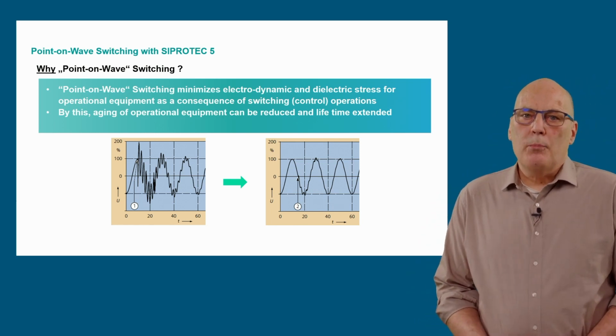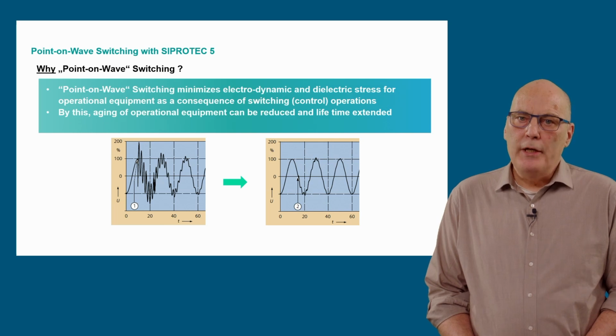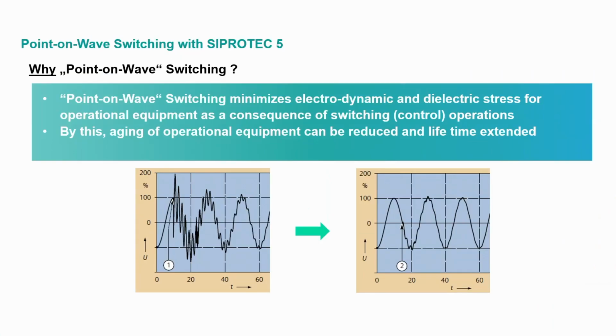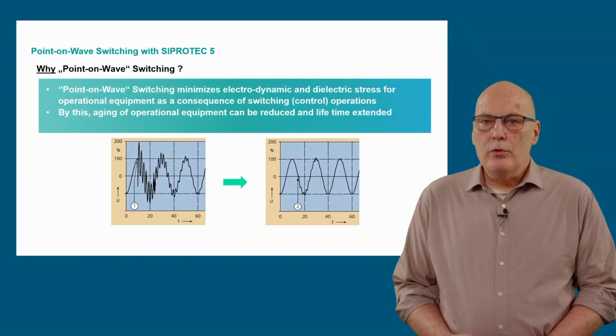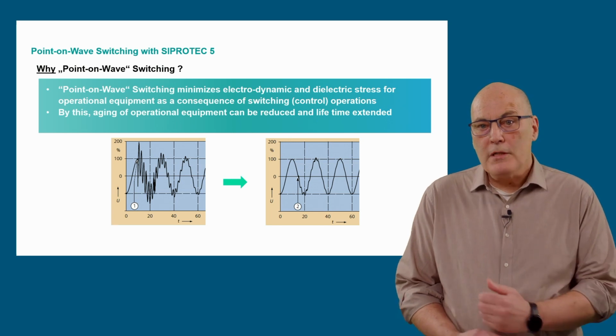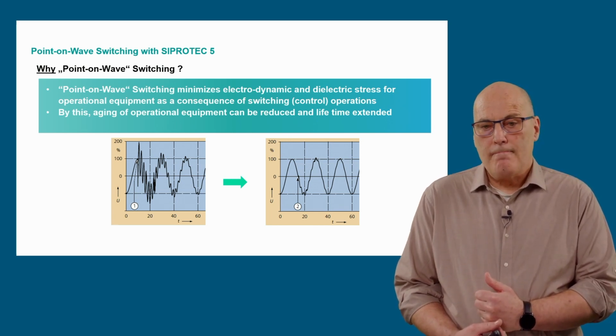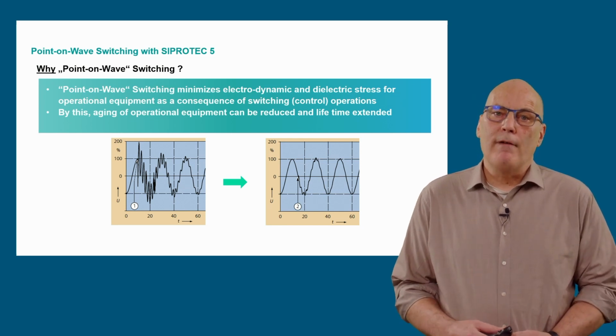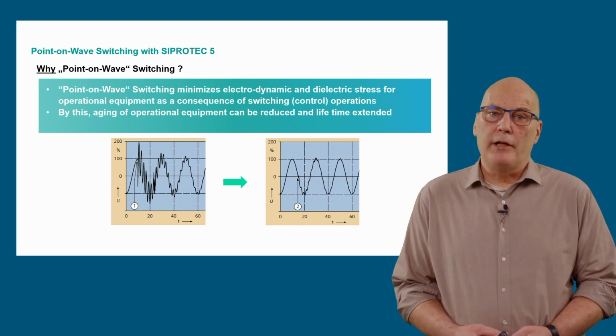To begin, where is point-on-wave switching a benefit? As shown here, a capacitive load or cap bank was energized. On the left side, the instant of closing was at voltage peak and severe voltage transients are seen. These transients have the potential to severely damage plant and equipment, including the energized capacitor. On the right-hand side, the same capacitor was energized correctly with point-on-wave switching, close to the zero crossing of the voltage. There are almost no induced transients due to the closure. So the advantage of the point-on-wave closing function is very clearly demonstrated in these diagrams.